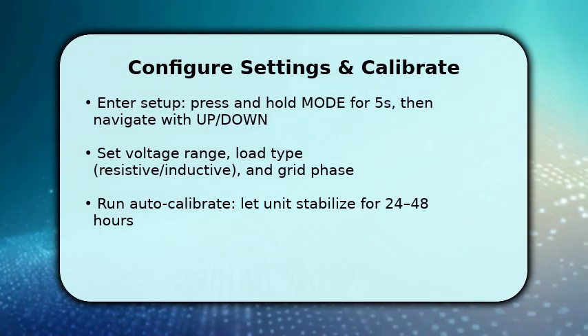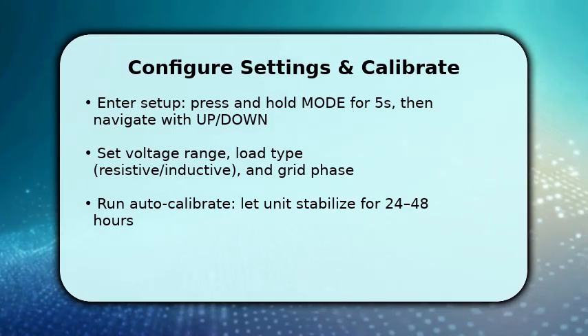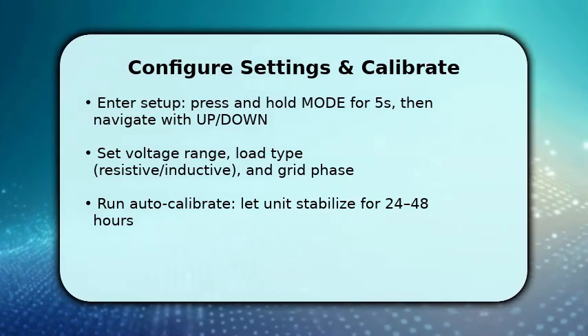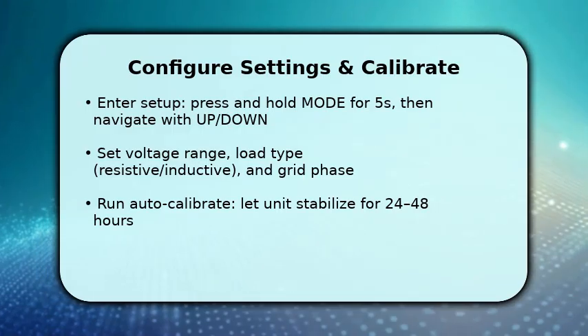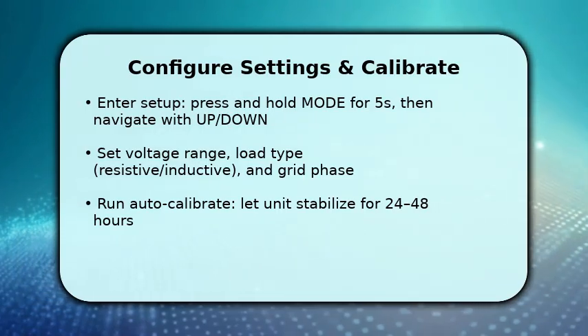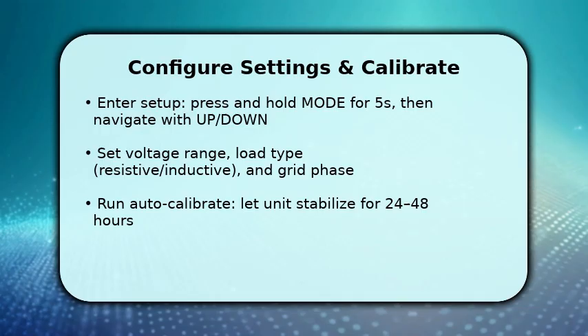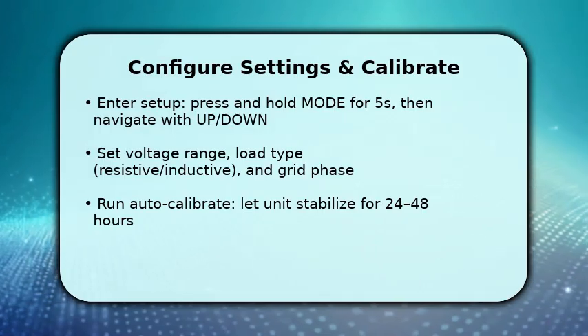Once options are stored, initiate auto-calibrate. The unit samples reactive and apparent power to compute correction profiles. Let it stabilize for 24 to 48 hours so algorithms adapt to daily usage patterns.